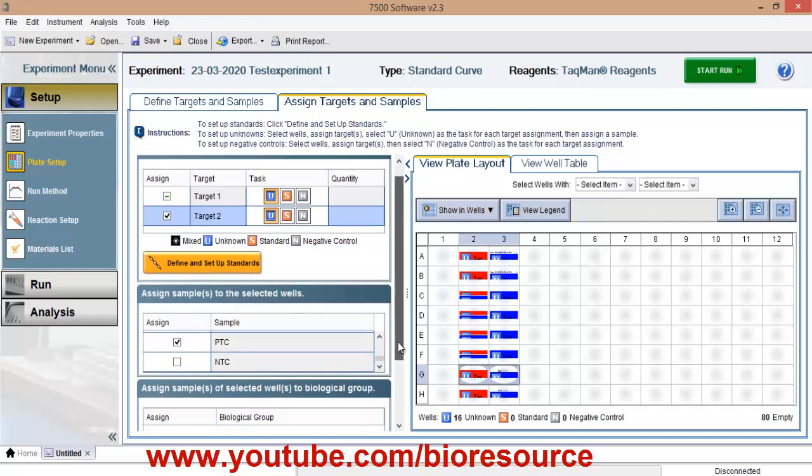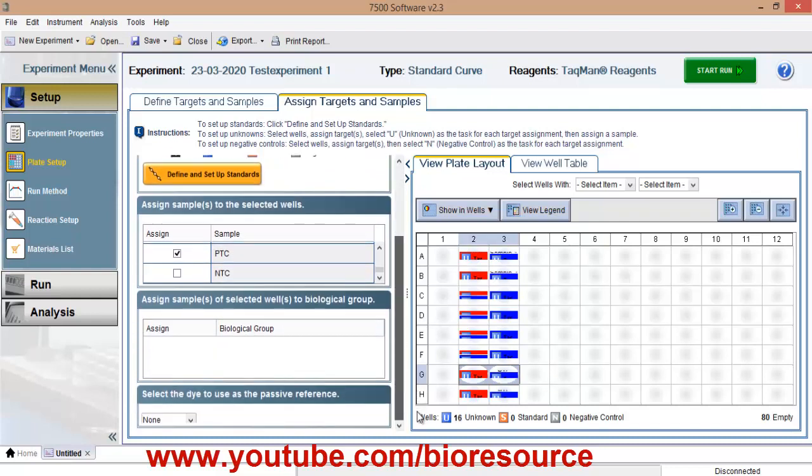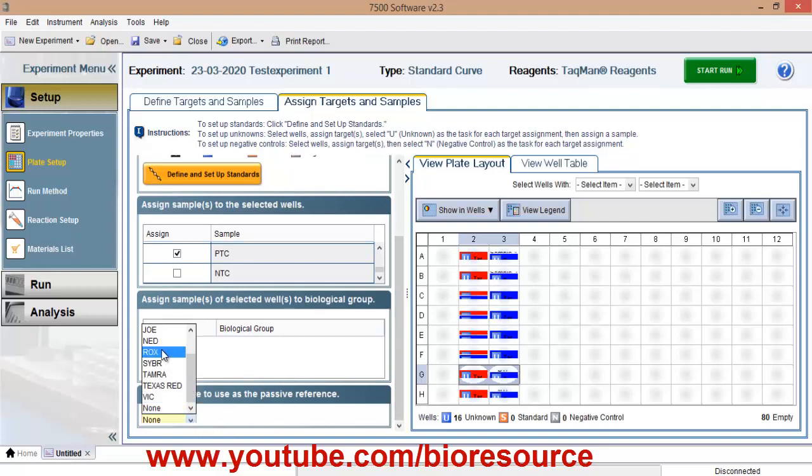So here you have the option to select ROX, passive reference dye. If your master mix is having a passive reference dye, you can turn this on with the respective dye. Otherwise you can keep this none.